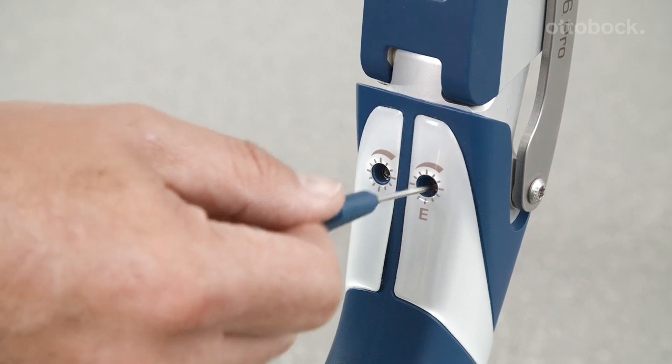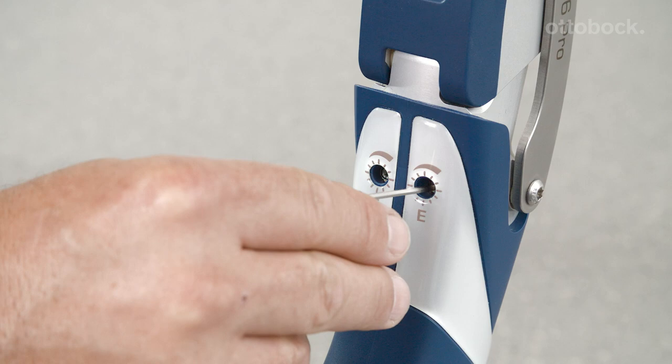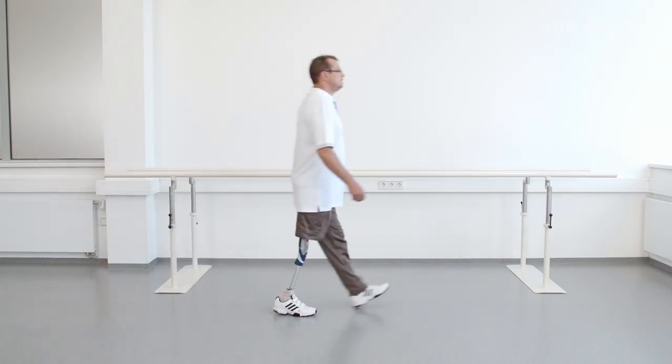Reducing the extension damping setting ensures that the leg will reach full extension at heel strike. In any case, the user should not feel a hard extension stop.